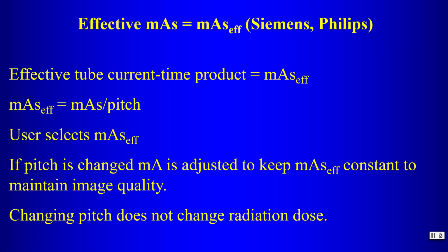So if the pitch is changed in your protocol, the MA is adjusted to keep the effective MAS constant to maintain the image quality. So with Siemens, changing the pitch does not really change the dose, as the system adjusts to keep this MAS effective constant throughout the particular scan.